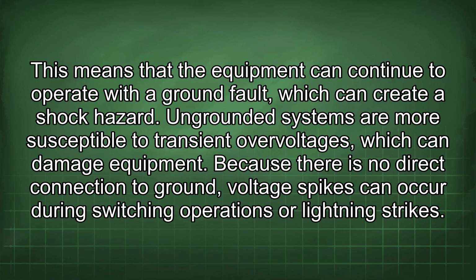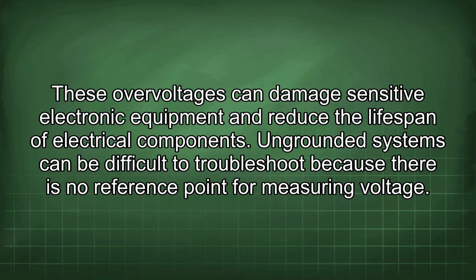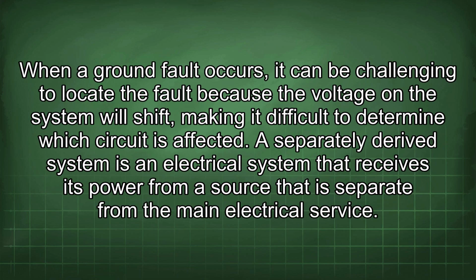Because there is no direct connection to ground, voltage spikes can occur during switching operations or lightning strikes. These overvoltages can damage sensitive electronic equipment and reduce the lifespan of electrical components. Ungrounded systems can be difficult to troubleshoot because there is no reference point for measuring voltage. When a ground fault occurs, it can be challenging to locate the fault because the voltage on the system will shift, making it difficult to determine which circuit is affected.